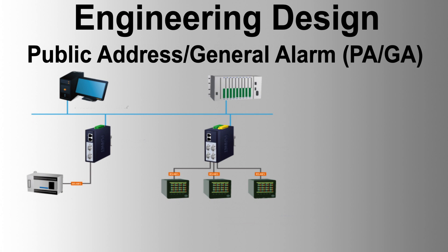PAGA master and local paging panels: master paging panels are located at operator consoles in each manned control center. Local paging panels are provided at administration buildings and guard houses. Audio-visual alarms are provided at remote stations linked to the PAGA system. Master and local paging panels support operator voice announcement and alarm control. Announcements are classified as routine or emergency, and paging panels interlock to prevent interference with calls in progress.